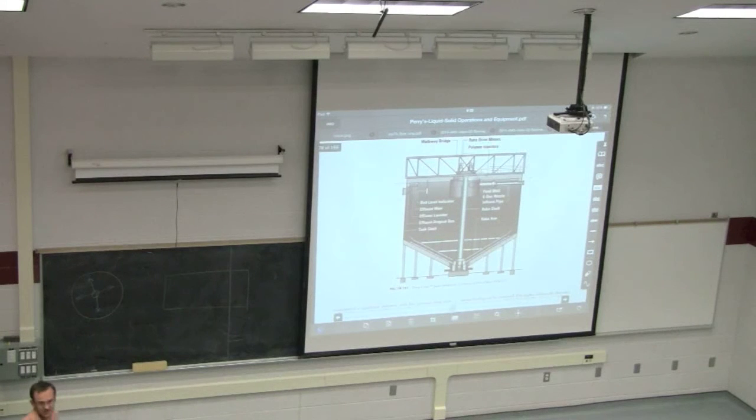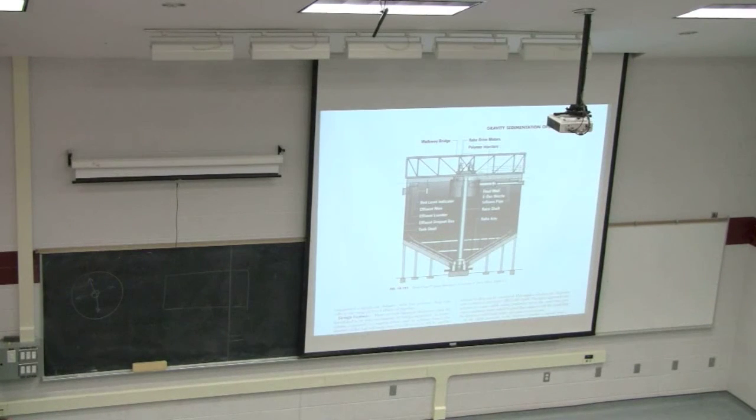So as you can see here, the material is fed at the top. There's polymer injectors, your feed is coming in at the top, and it's dispersed here. And that feed will flow in a radial direction to the outer edges. That's the effluent weir and the effluent launder. So that's taking the overflow, the liquid, out. The solids settle down to the bottom. There's this rake that we spoke about, and the solids are withdrawn through those two points at the bottom.